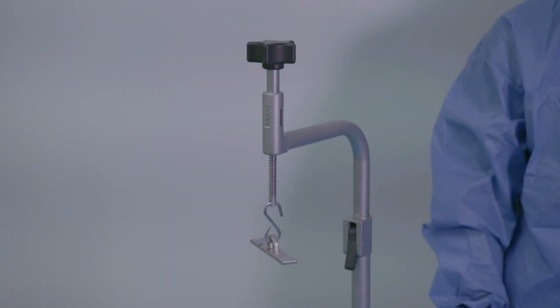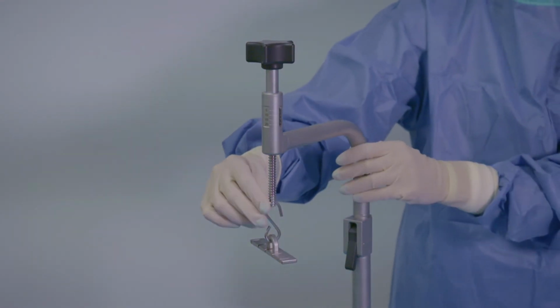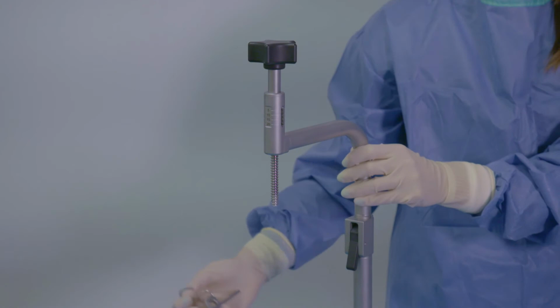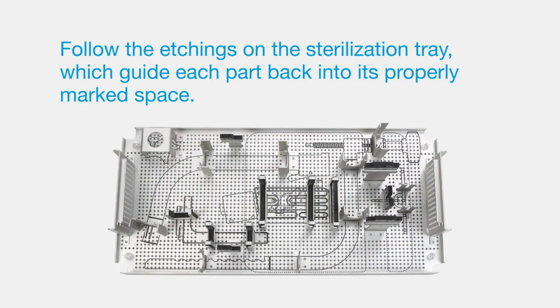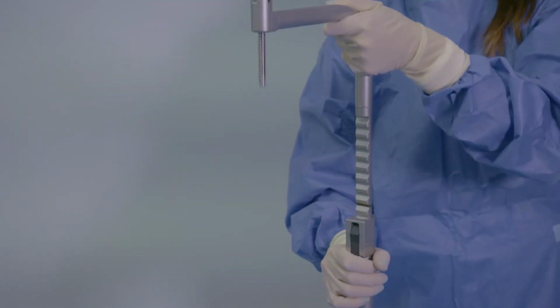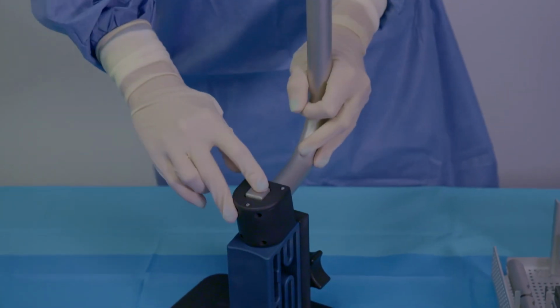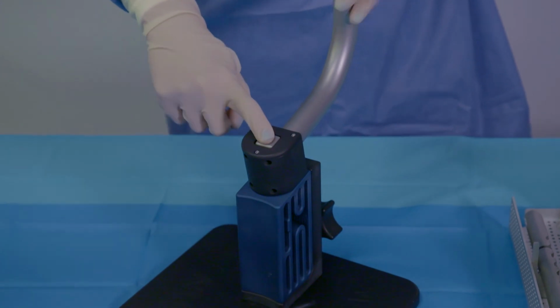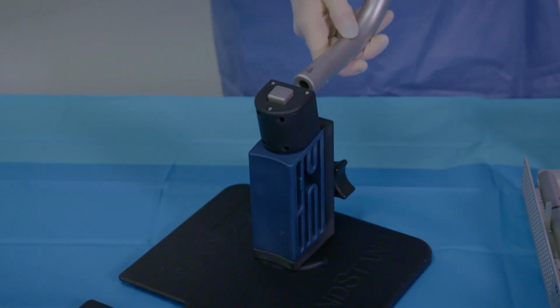To disassemble the tower, first remove the scale rack from the threaded rod in the upper arm. Follow the etchings on the sterilization tray, which guide each part back into its properly marked space. Next, depress the black lever on the lower arm and remove the upper arm. Then depress the silver button on top of the upper tower to remove the lower arm.